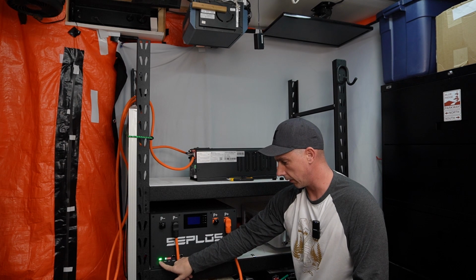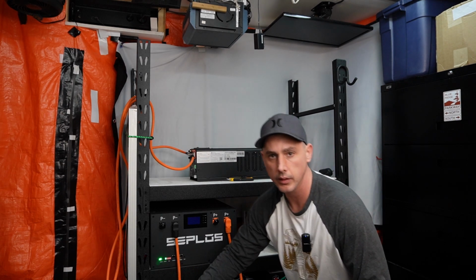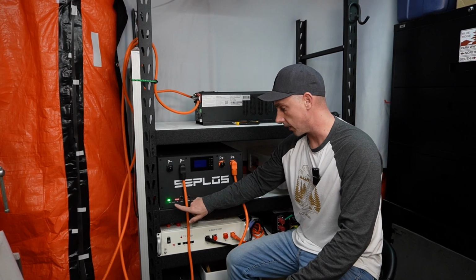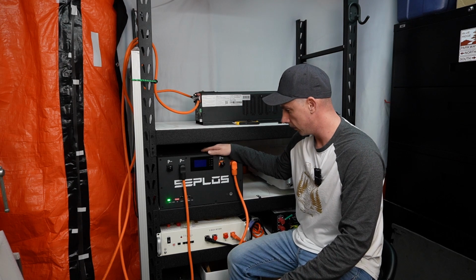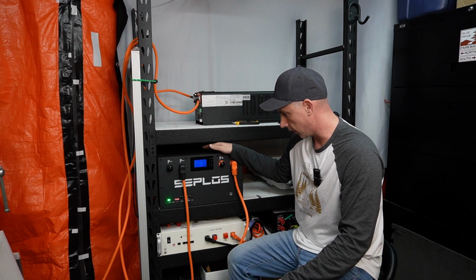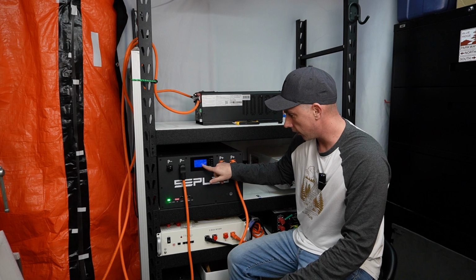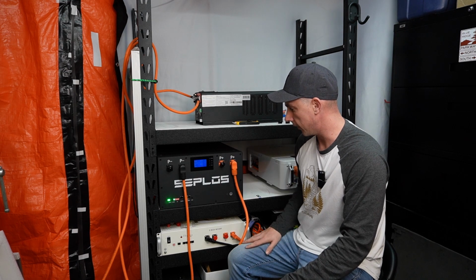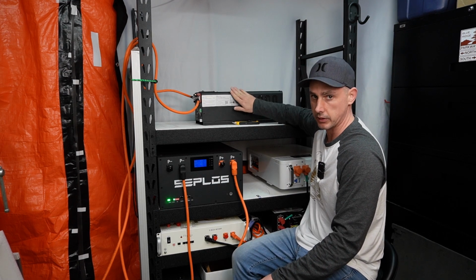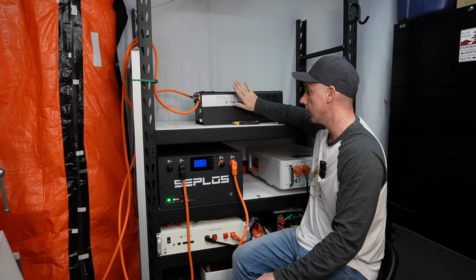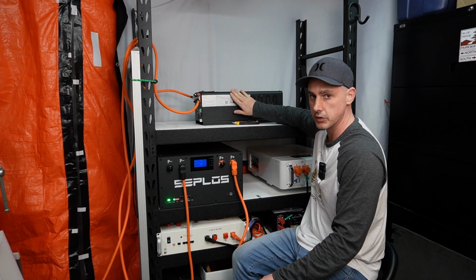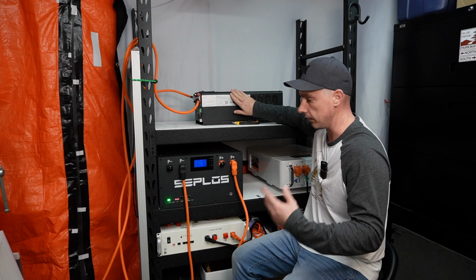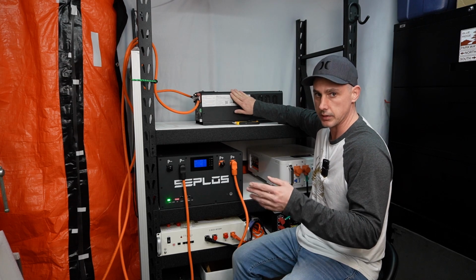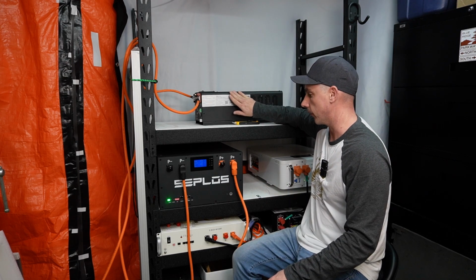Oh, there we go. Now we can see the capacity lights lit up on the front of the case. Let's turn the screen on - we're currently drawing 1.11 amps, which is the standby consumption. This is a low frequency inverter, so it has high standby consumption because there's a transformer inside that it needs to power in order to create a split phase 240 volt output.